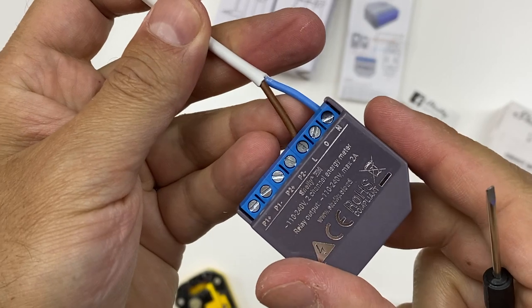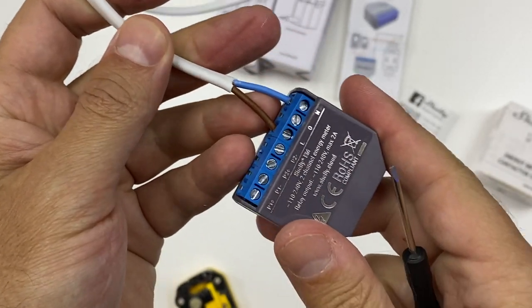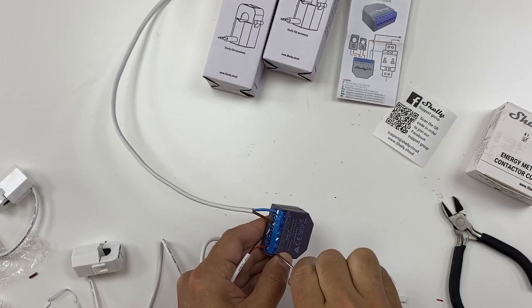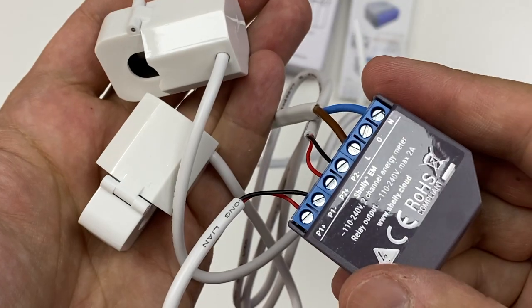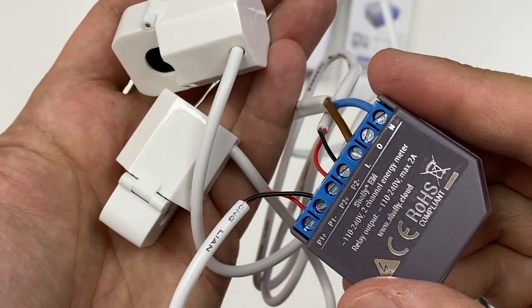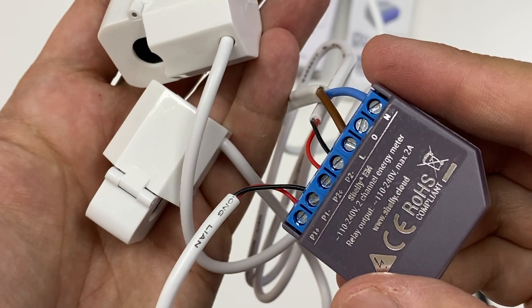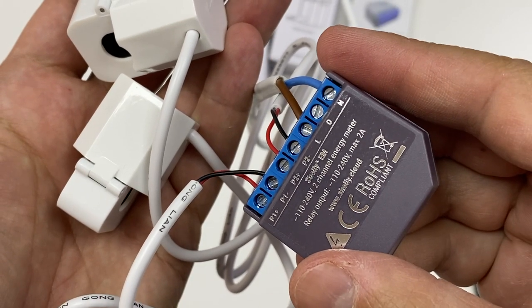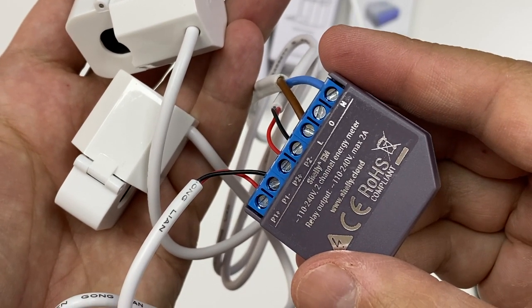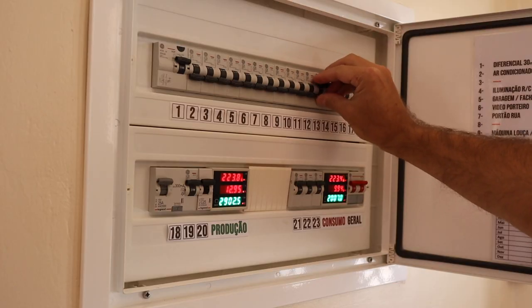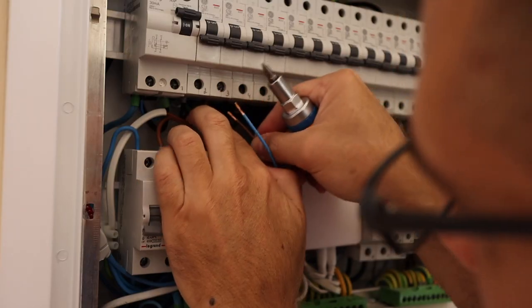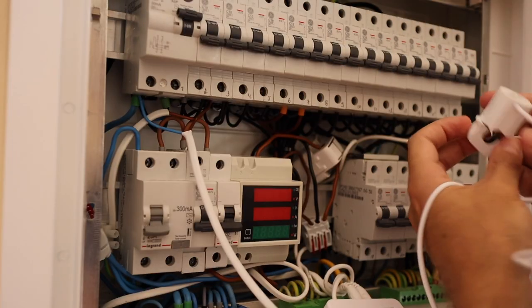To power the Shelly EM, all we need is a phase and a neutral wire. Basically, that is it. And then we just need to put in the cables for the clamp. In my particular case, 2 clamps, so 2 wires each clamp. And as you can see, black and red, and that's it. After that, we will go to our circuit breaker, shut everything down, and I just need to connect the phase and the neutral wire to power the Shelly EM.